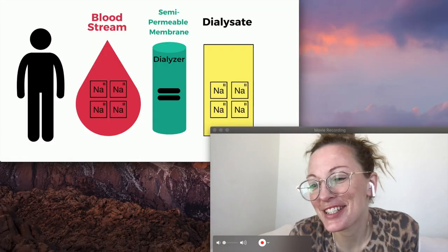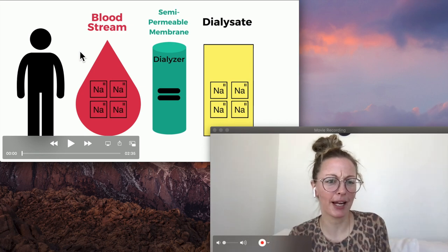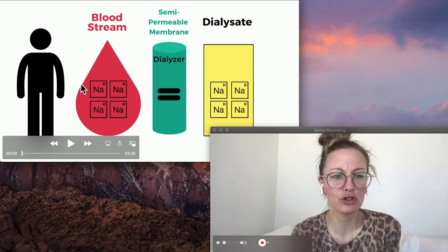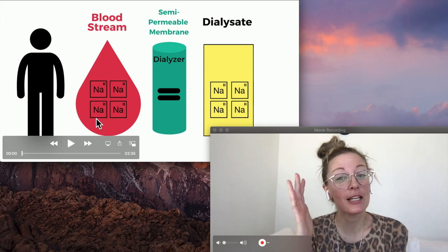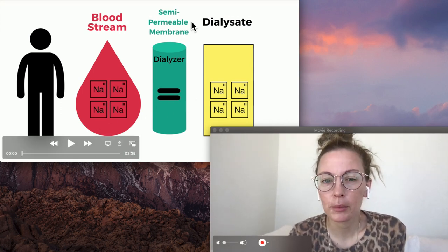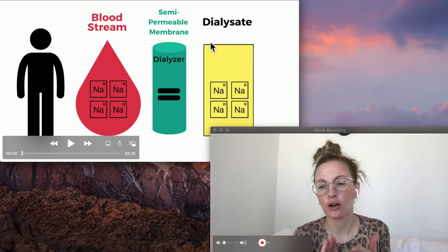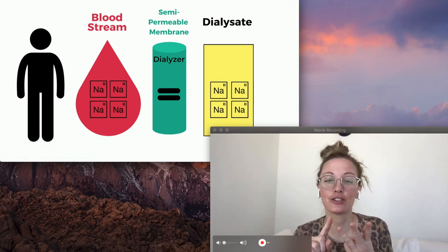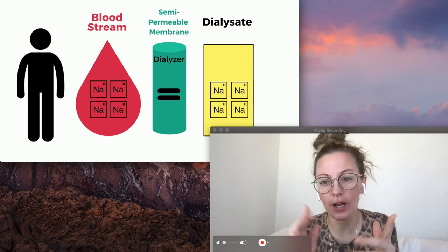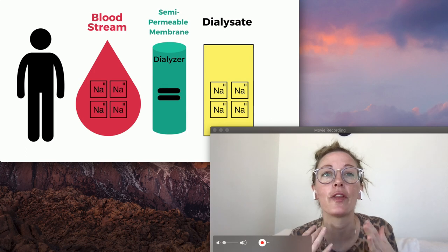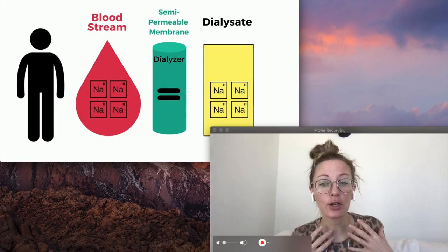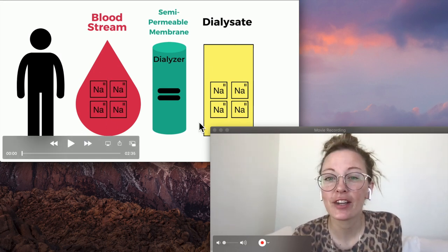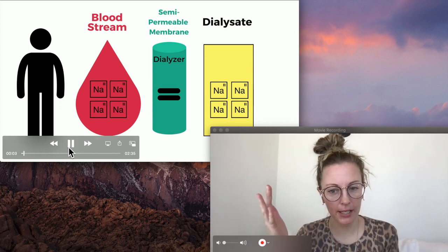Welcome to the inside of my dialysis machine — and kind of the inside of my brain. On the left we have the dialysis patient, and inside the dialysis patient we can see their bloodstream, or intravascular space. Then we have the dialyzer, the semi-permeable membrane. And on the far right we have the dialysate — a mixture of purified water, acid, and sodium bicarb. A normal serum sodium level in a person is 135 to 140, so here the bloodstream is at 140 and the dialysate is also set at 140. Machine conductivity: 140. Conductivity equals sodium.